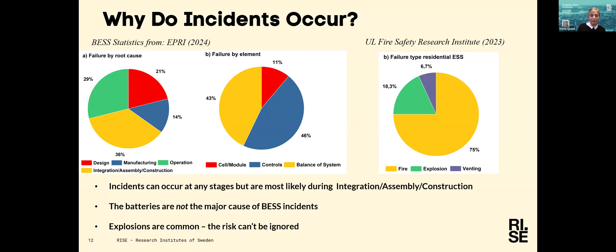UL have also looked at failure types in residential energy storage systems. In 6.7% of cases, gas was vented but there was no fire or explosion. In 75% of cases, there was a fire related to the incident, and in around 18%, there was an explosion. So explosions are common, and the risk of explosions cannot be ignored when we speak about battery safety.